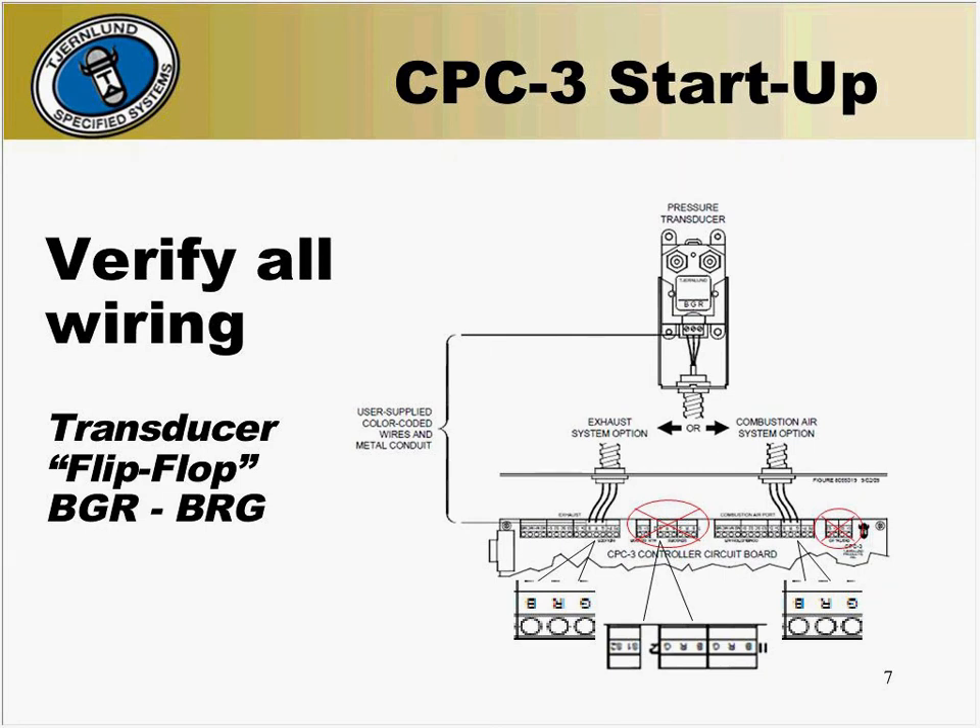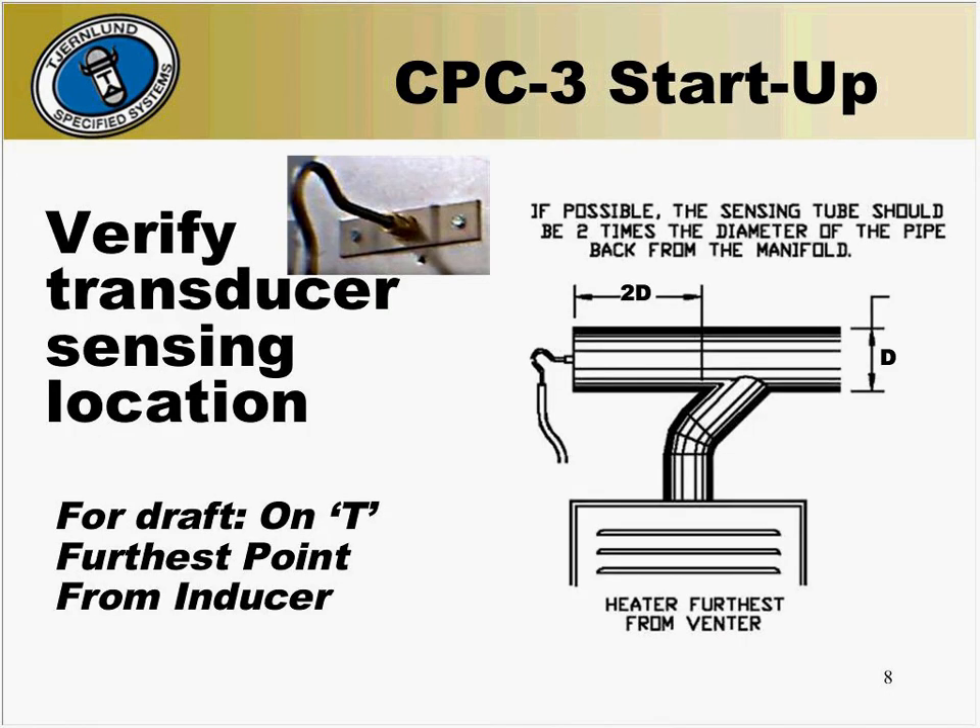There are two other B, R, and G terminal blocks at the top center of the board — these should not be used. Finally, verify that the transducer is properly located. For a draft application, in a perfect world, it would be on a tee two times the diameter of the vent pipe back from the manifold at the furthest point from the inducer.